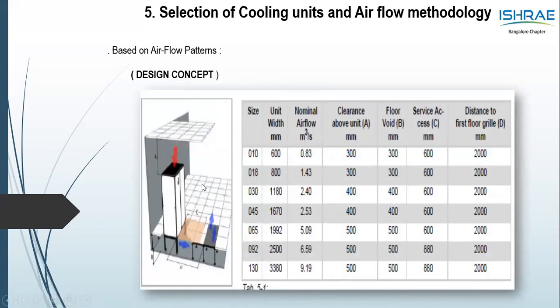Apart from that, very important is that we cannot place the PAC in any direction and say that, yeah, the PAC is going to do the job and I have the best cooling in the world and it's going to do the right job for me. The answer is that it is very important that we place the CCU in the correct location. Number one, based on the airflow from these units, look at the return air. We want sufficient gap for return air. For example, for case number one, we would want a minimum of 300 mm to the unit.